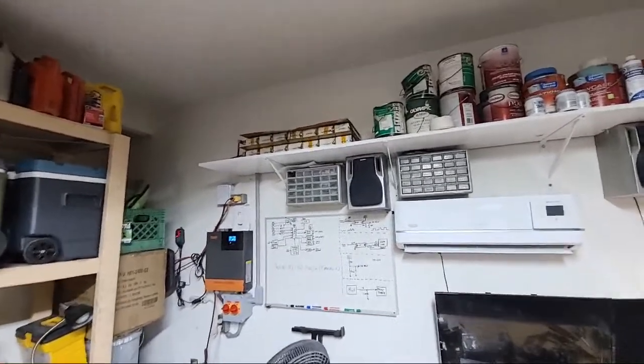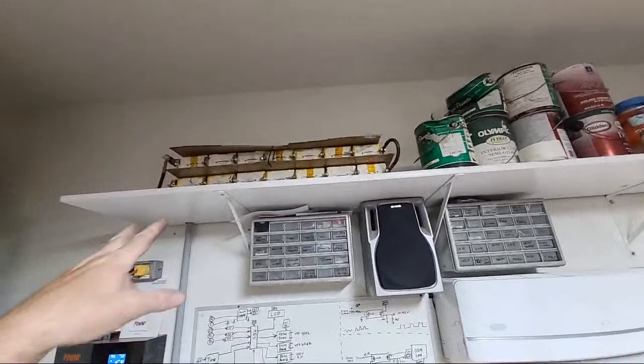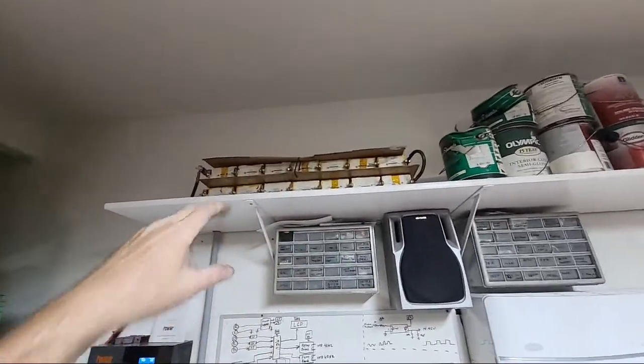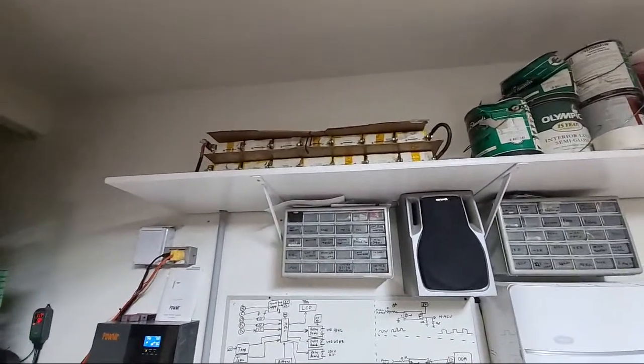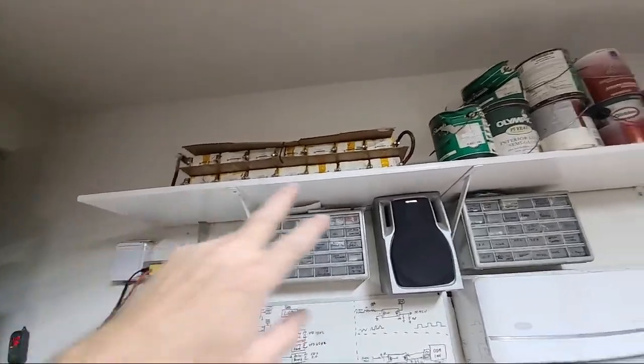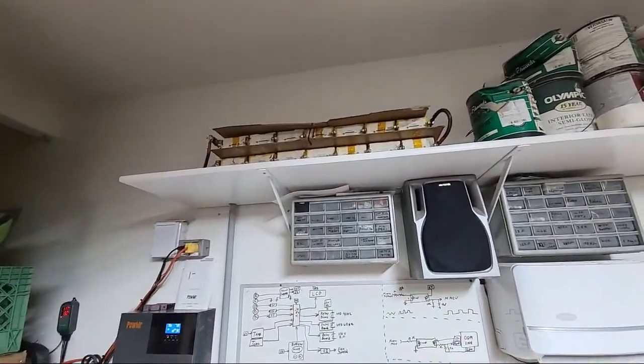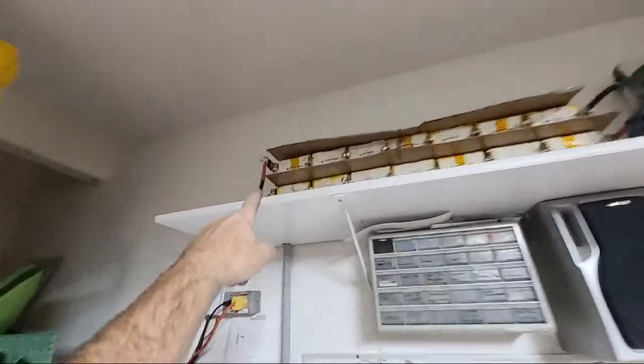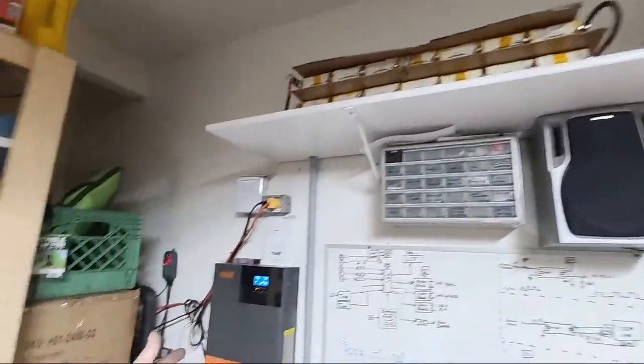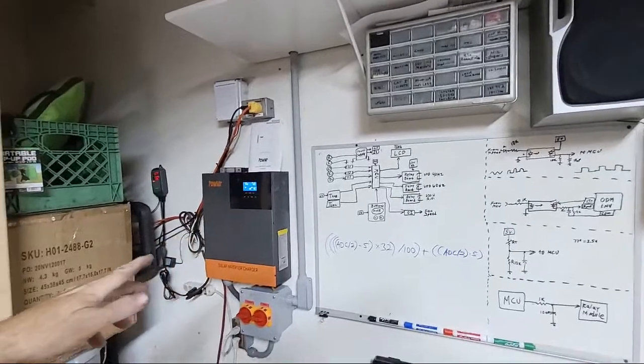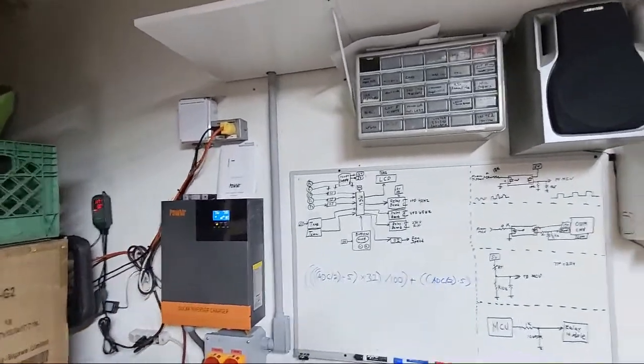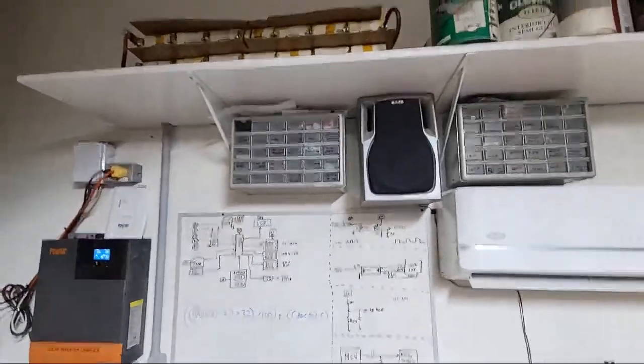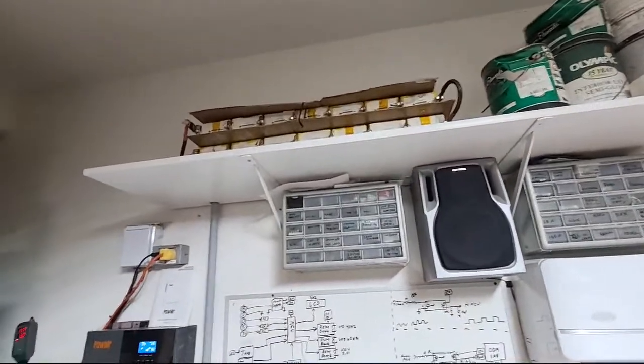I could have put 13 of these in series and charged them to their peak for the 48 volt nominal, but I actually did 14 per recommendation. I also have a 100 amp fuse I put in there because I did not dare hook that thing up without a fuse. So 14 in series, charging it to 57 volts, which puts it a couple tenths under its full voltage range that's acceptable on those.